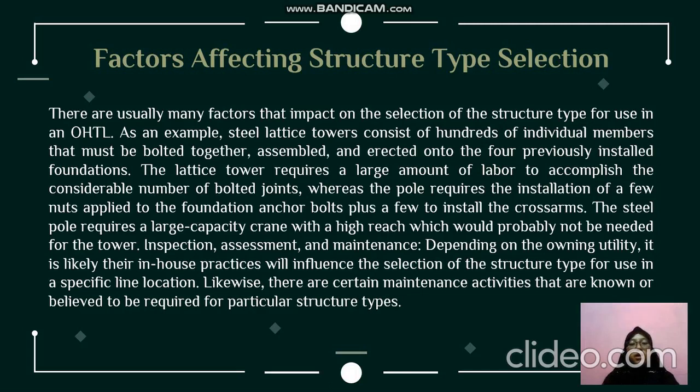The lattice tower requires a large amount of labor to accomplish the considerable number of bolted joints, whereas the pole requires the installation of a few nuts applied to the foundation anchor bolts, plus a few to install the crossarms. And the steel pole requires a large capacity crane with a high reach, which would probably not be needed for the tower.